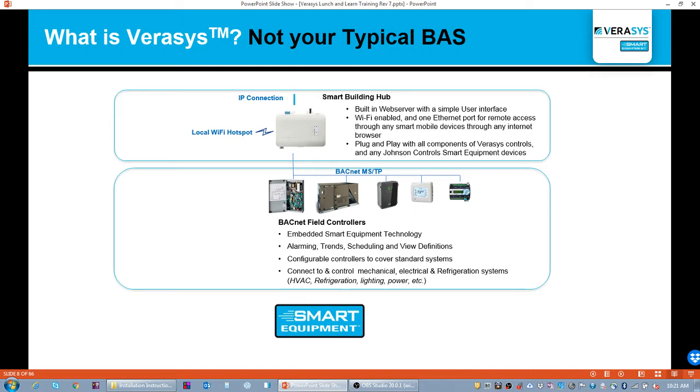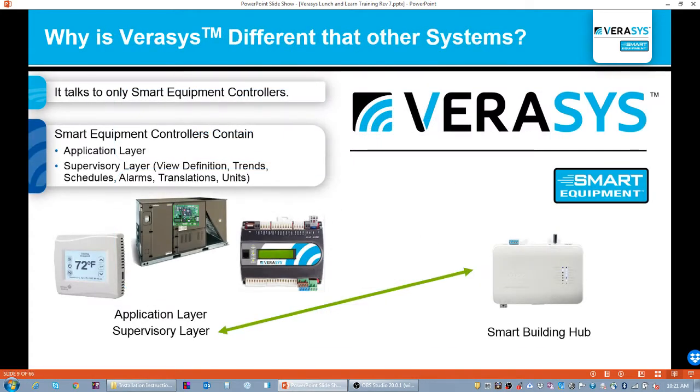So when we connect up a controller in Verasys and address it, the device will automatically appear in the Verasys windows and connect up appropriately to whatever systems we have. So let's recap what I mean by that. I have these smart equipment controllers, whether it be a rooftop unit, an application controller, or a TEC thermostat. They have what I would call an application layer already built into them. That does the function of the rooftop or controls whatever it would be. So that's normal. That's what typically you'll have on a controller.